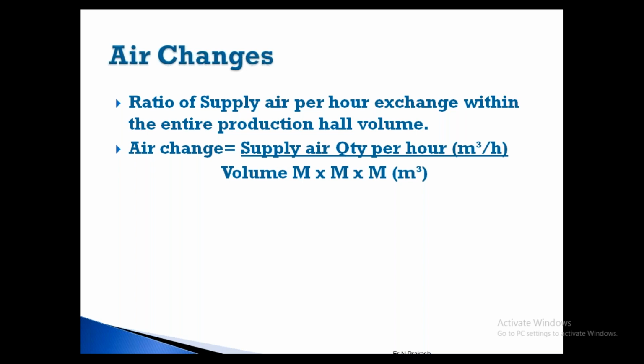We have to find out whether this production problem is coming because of the air changes. You set particular air changes and everything is fine, working will be fine. Suddenly they will change the product count and mixing, everything they will change. So suddenly there will be some disturbances in the process. Immediately they will tell that it is due to improper air changes. So when we go for energy conservation, when we change the blade angle of the fan or reduce the speed of the fan or multi-fan system, we have to consider everything. It should not backfire.